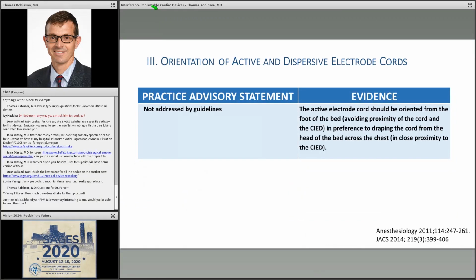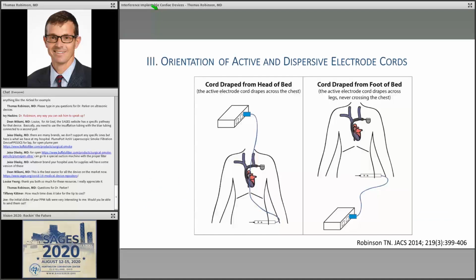So we have orientation of active and dispersive electrode cords. It turns out that the active electrode cord and the dispersive electrode cord both radiate electromagnetic interference. So if you're operating on a patient with an implanted cardiac device, you want to put your electrosurgery generator at the feet so you can drape the cord up from the feet, so that the cord does not drape over or adjacent to the pacemaker. The image on the left is how you should not do it, because you're going to get more electromagnetic interference on your cardiac device. Whereas the image on the right, where you keep the cord draped up from the feet, is the way you want to do it.